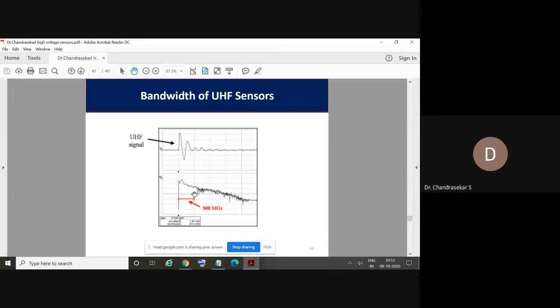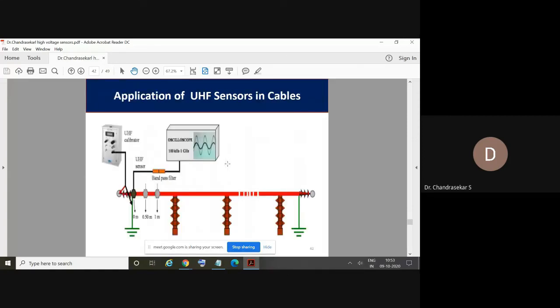As I already told, the bandwidth of the UHF sensor is almost in the range of 500 megahertz, so ultra high frequency. So this is simply connecting UHF sensors in an underground cable. When we connect it, this is how they are measuring using a UHF calibrator. I have a small video of a UHF sensor also. I will show you that one.